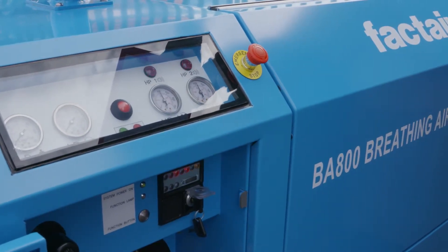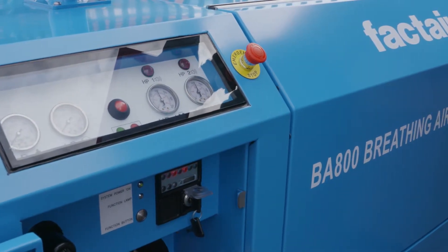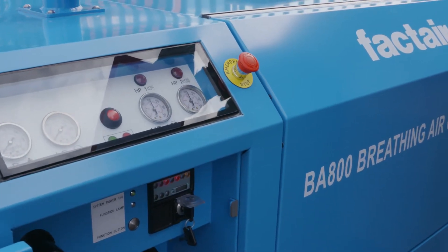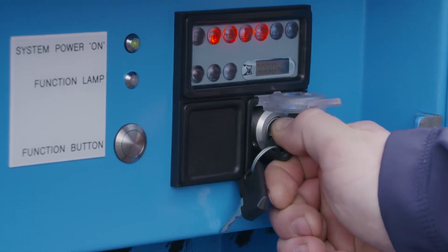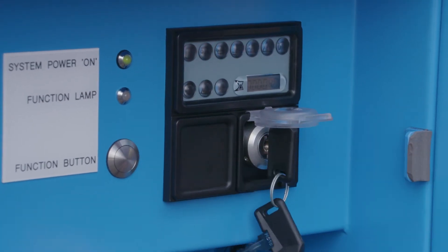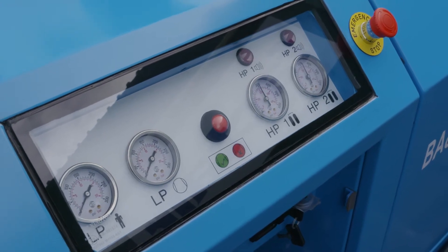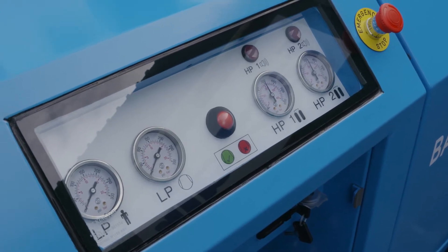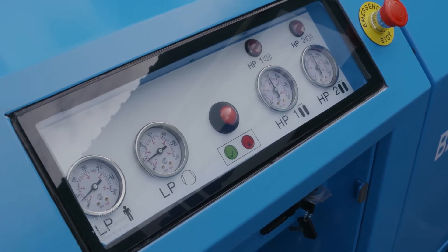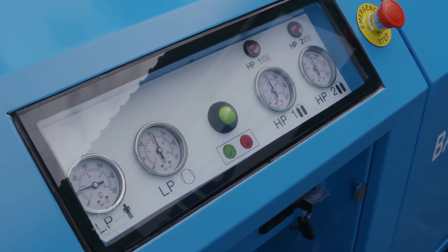While this is happening, the two red LEDs will flash and audible alarms will sound. If this test finds that it is satisfactory, the LEDs will go out and the engine preheater will be energized. After a few seconds, the audible alarm tone will change and the engine can now be cranked. To do this, turn the start switch to position 2 and hold it for 10 seconds, or until the engine starts. Don't try to crank the engine until the alarm sound changes or the whole process will need to be repeated. The engine will start and run up to full revs, but no pressure will be produced until the engine is warm. The compressor will then load up, the status indicator will go from red to green, and the audible alarm will be silenced.